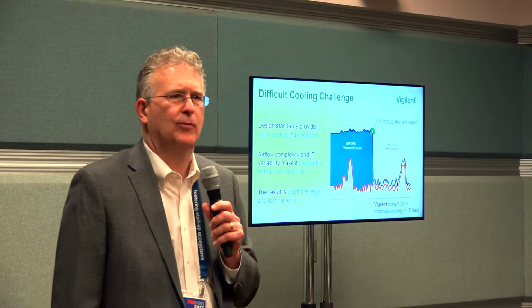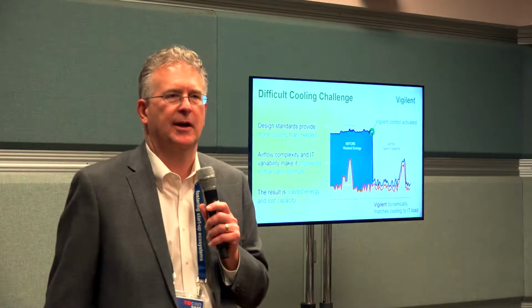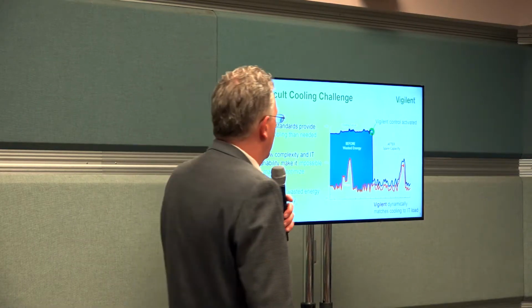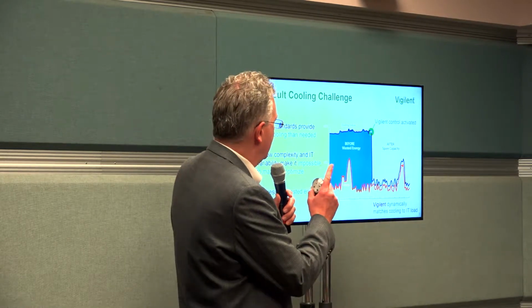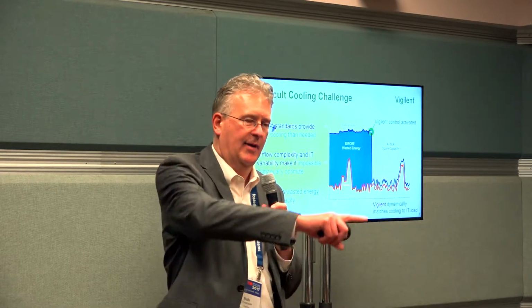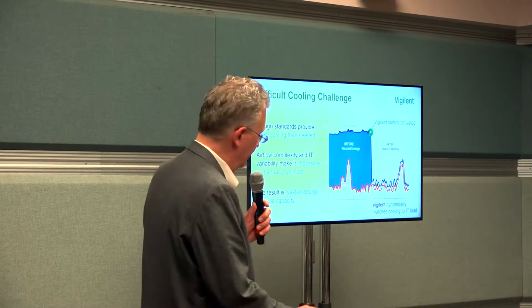You also end up with a bunch of wasted capacity, you've spent too much money on air conditioners. So what Vigilent does is use our technology to match the cooling to the IT load at every spot in the room dynamically, in real time. So you save a huge amount of energy, you have extra cooling capacity you can use elsewhere, and your cooling equipment isn't used as much, so it lasts longer. There are a lot of benefits.